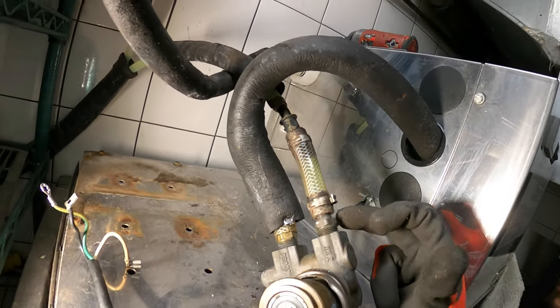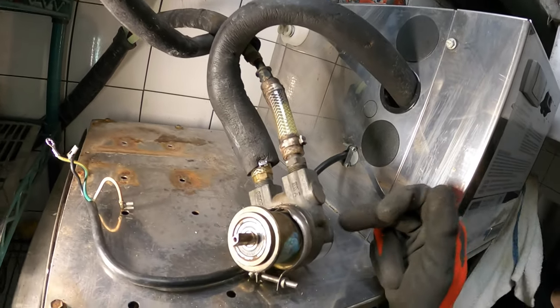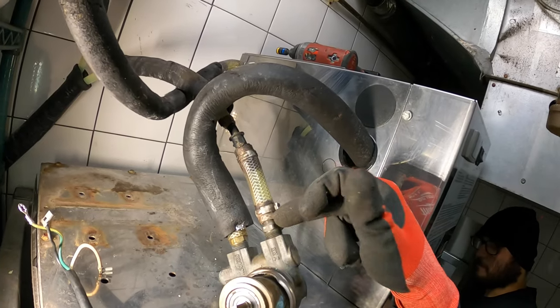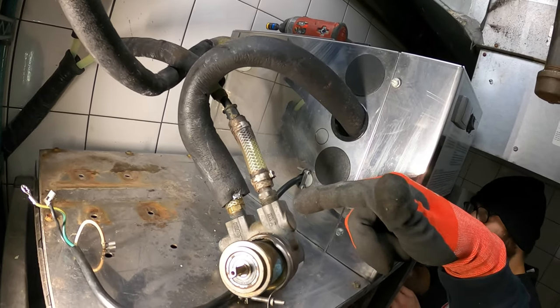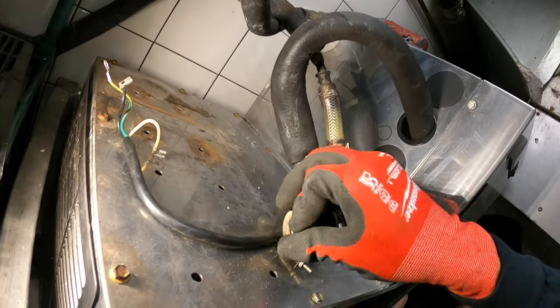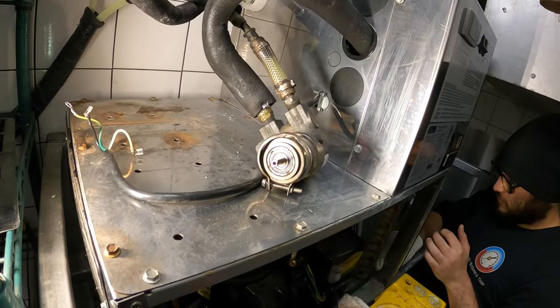They've got these clips on here, and there's fluid in here — I do not want to lose that until we change this pump. Let's just try to get them going for now. What I would like to do is try to clean this out, take off these hoses, run pressurized water through it and see if there's any gunk inside. This thing definitely locked up, but that's because of all the rust we saw on the old motor. Let's go ahead and get that new motor in.